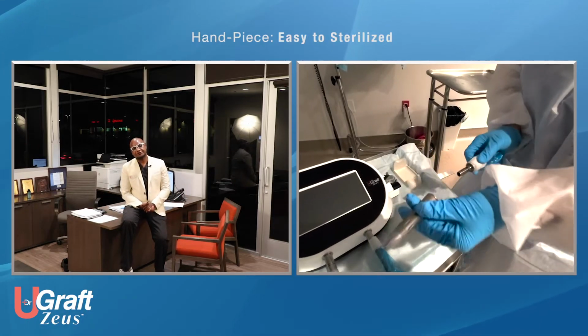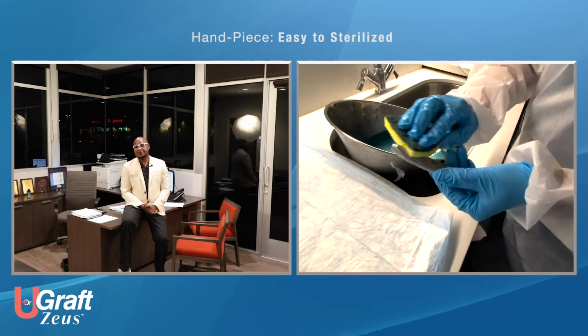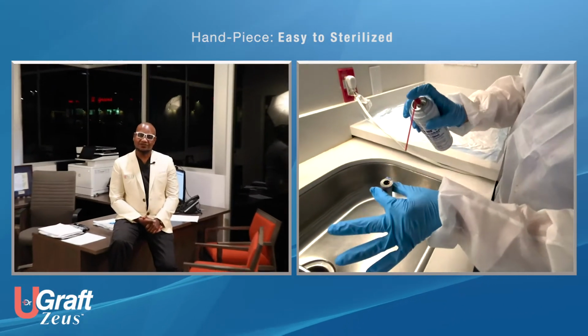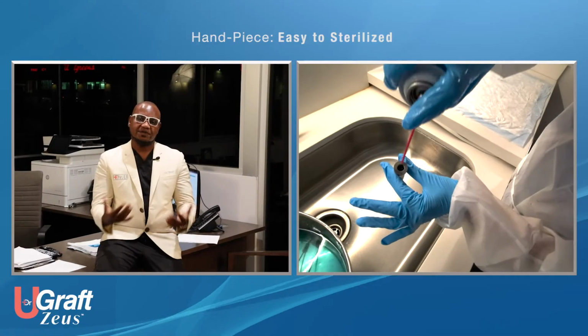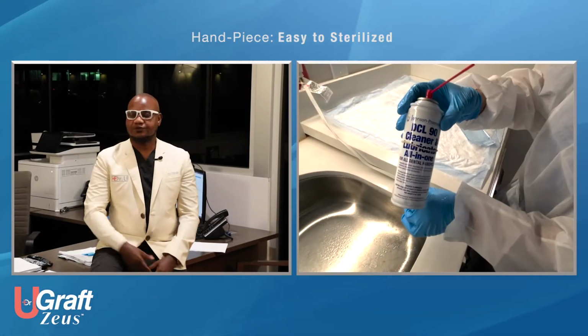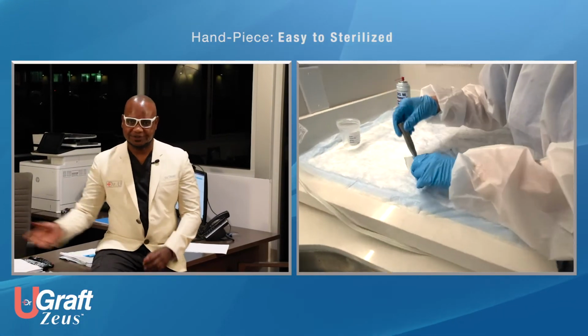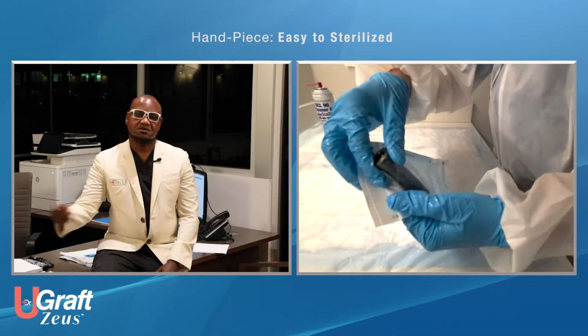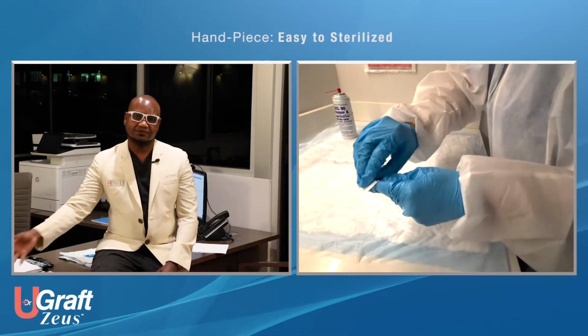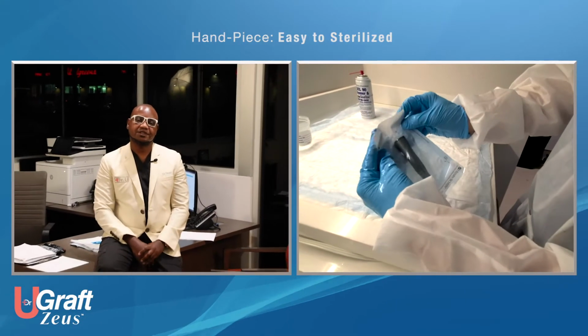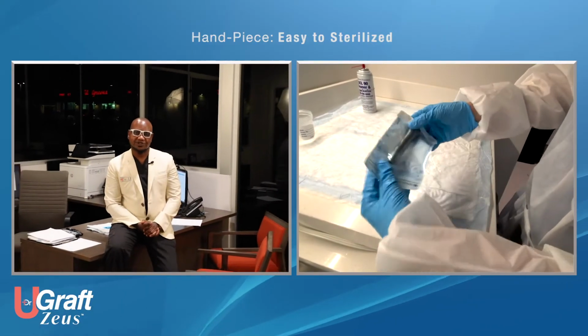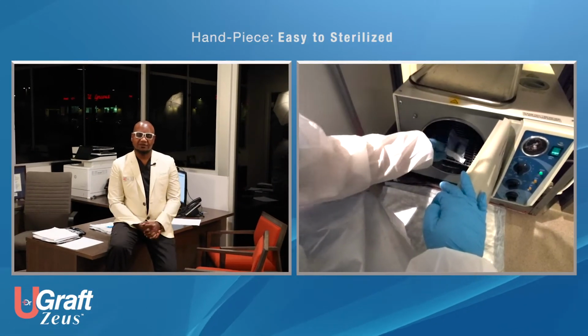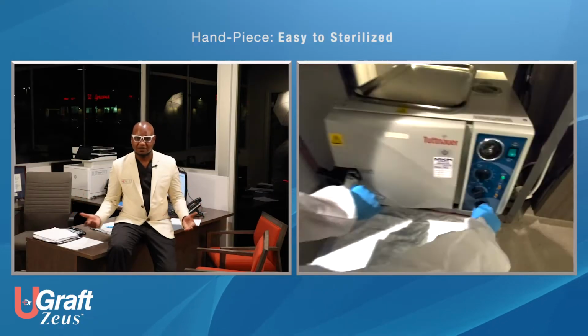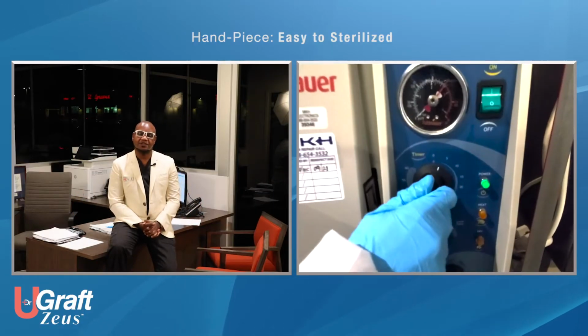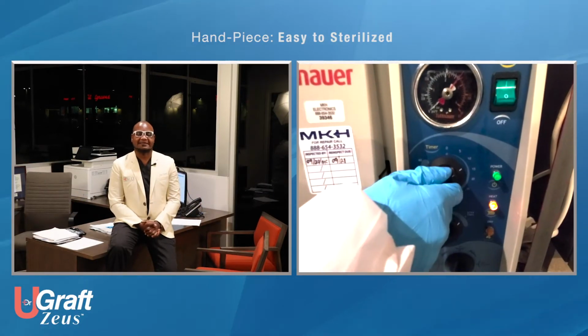The other advantage of this is that maintenance or sterilization is easy. It means to autoclave, you have the same approach as you do for the very generic, conventional machines. Basically, soak in detergent, pour a drop of lubricant, and put it in the autoclave machine. No special cleaning, no untoward protocols required to keep this machine autoclaved, sterile, and compliant.